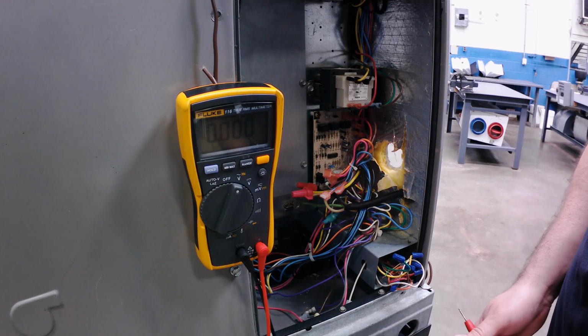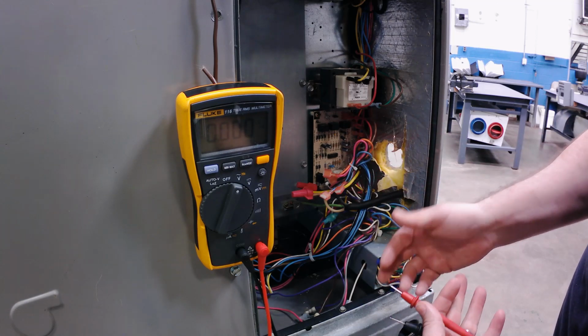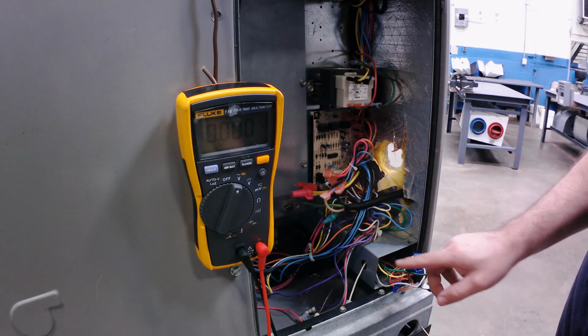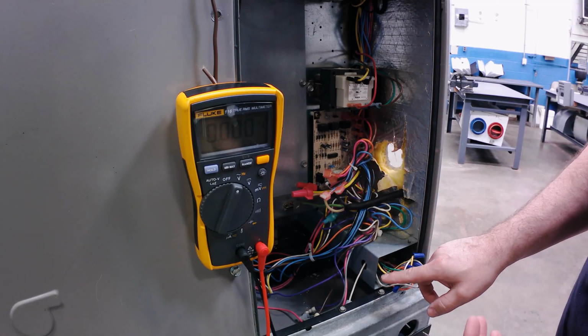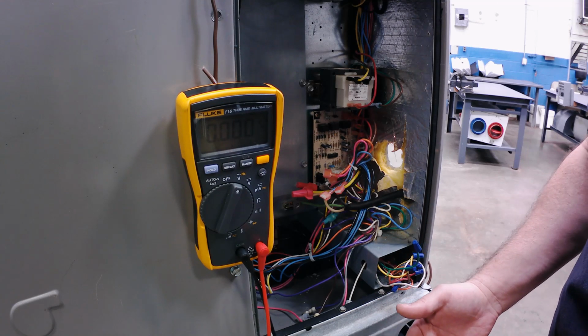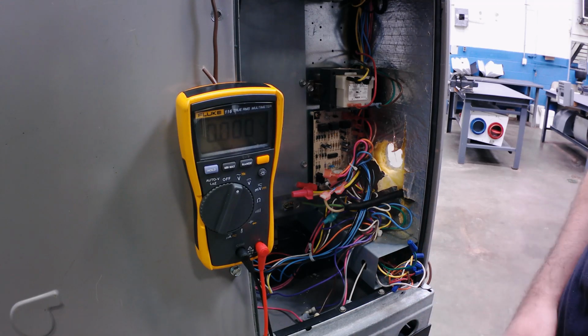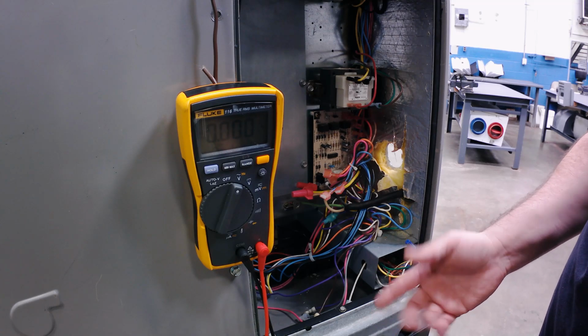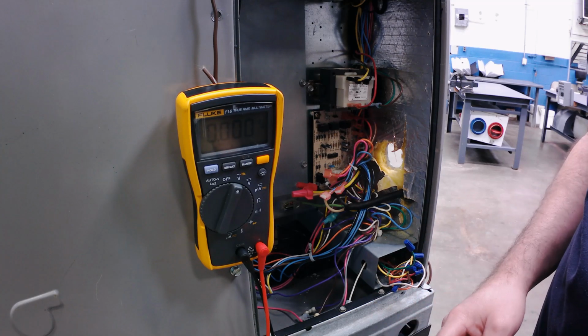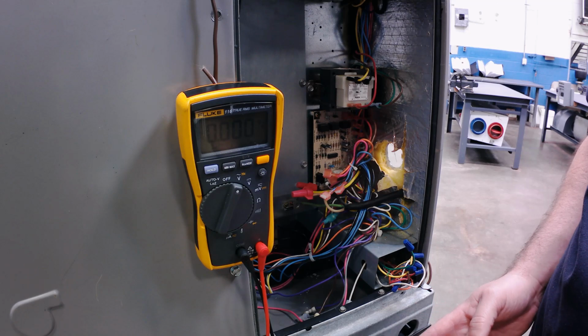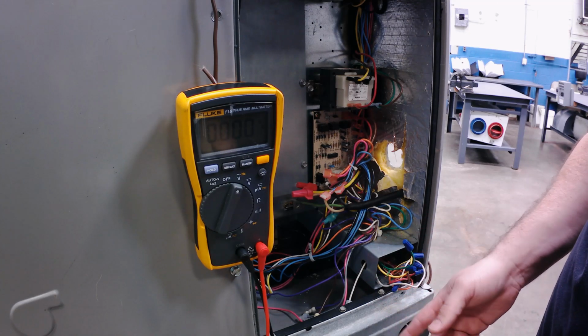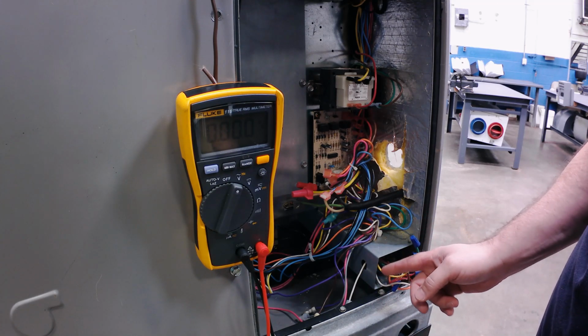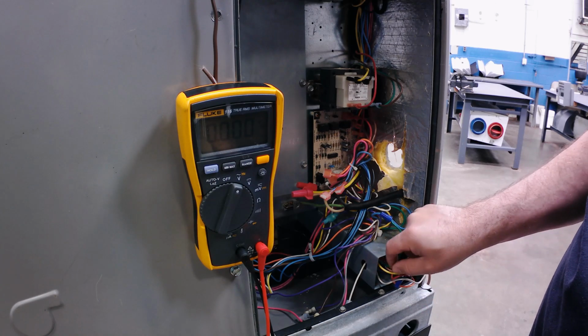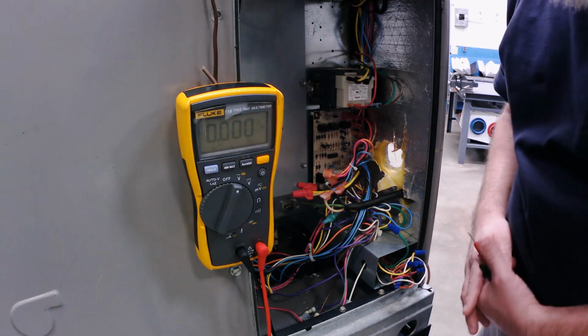What I'm going to do is check another circuit, like Y or O, to find out. I try to troubleshoot as much as I can to gain as much information. But if we were in a call for cooling and I checked G to common and got 0, but checked Y to common and got 24, then that's just one problem with that circuit, the G circuit.